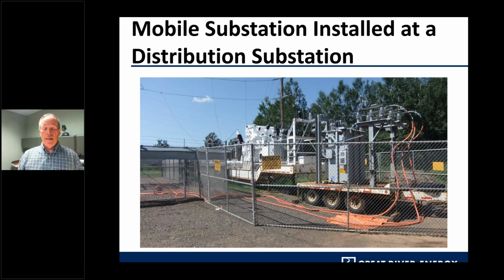Along with that, on each mobile we have a communication package that goes back to our system operations. GRE has their own private radio network, a 450 megahertz radio network that gives us real-time loading and status updates of the mobile. So if the recloser ever has to open, we'll know right away from our operations center that there was an outage, and we'd have to send individuals out to investigate why that opened. Otherwise, we can continue to monitor real-time loading on the mobile substation so there isn't any overloading or other issues.